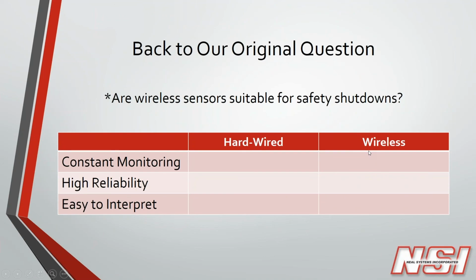I've set aside a couple different requirements for safety applications. The first is that for any safety application, if you've got people working on these assets or nearby, you need constant monitoring. I mean, you can't wait hours, weeks, even really minutes between taking samples. And the next one, you need to know that when there is a problem, you've got a very high reliability factor between catching that problem and having it turn the machine off or notify somebody of what procedures need to happen.